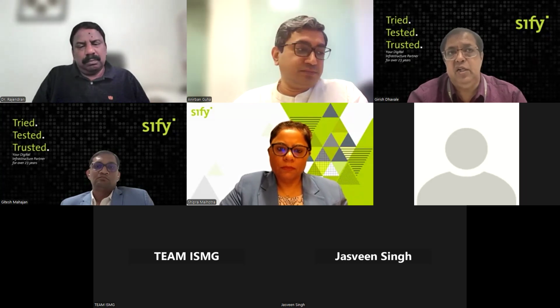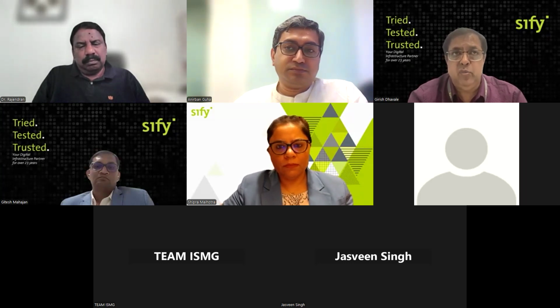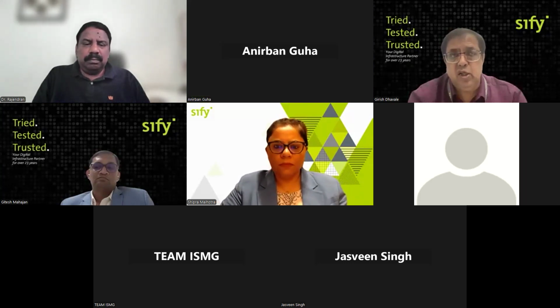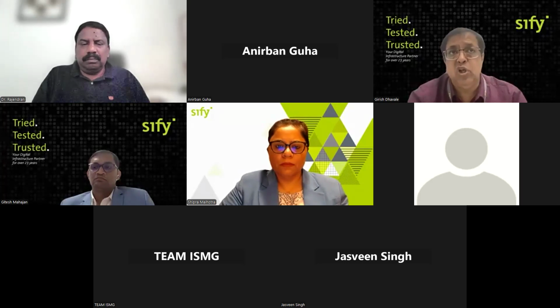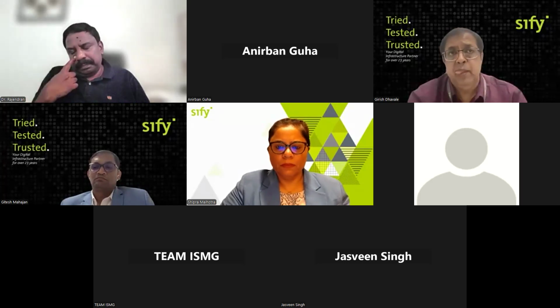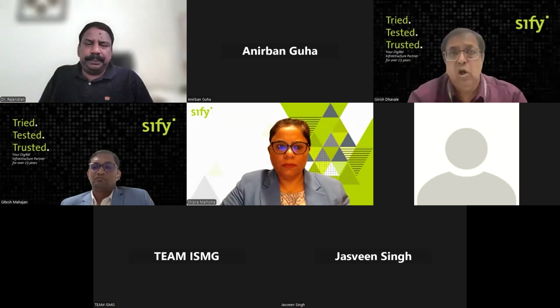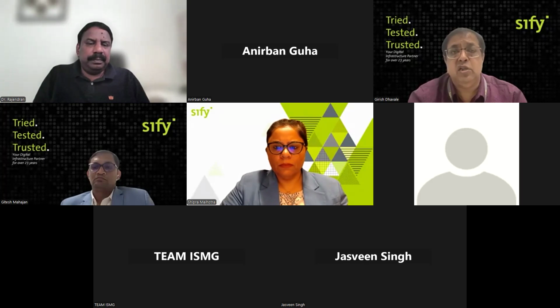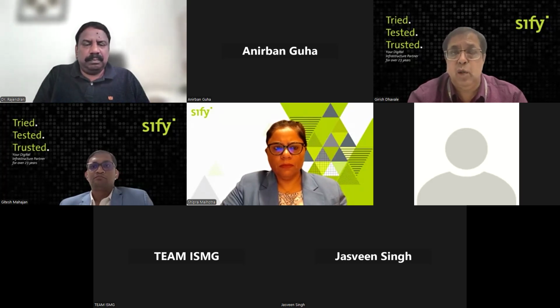Third, the new technologies now demanded by server manufacturers, as I mentioned in my presentation, include a rear door heat exchanger for more efficient heat rejection than conventional systems, chip-level cooling, or immersion cooling, where servers are immersed in a dielectric liquid whose temperature is maintained through a separate refrigeration cycle. The data centers are capable of handling all those technologies.